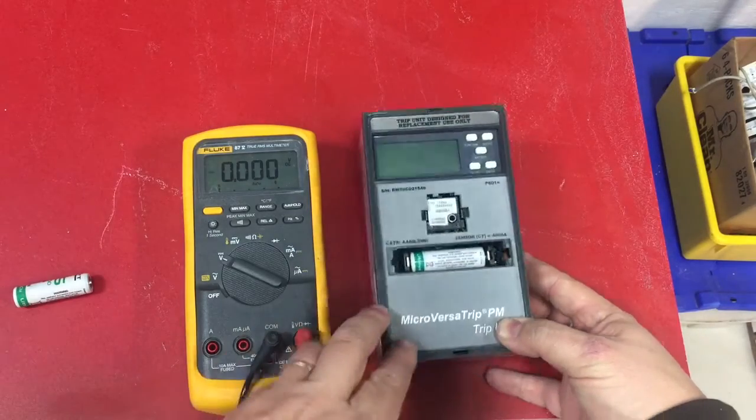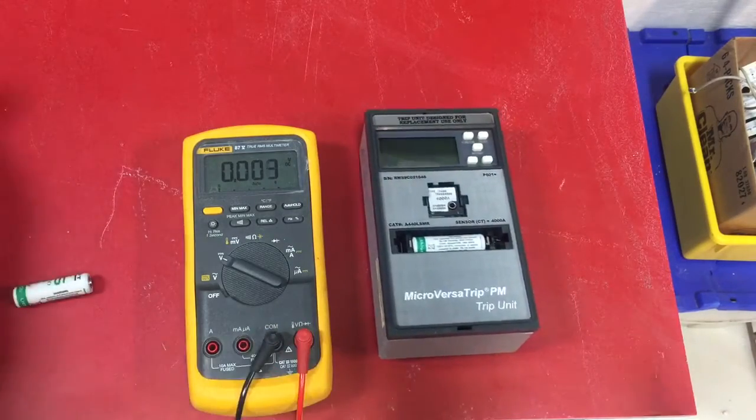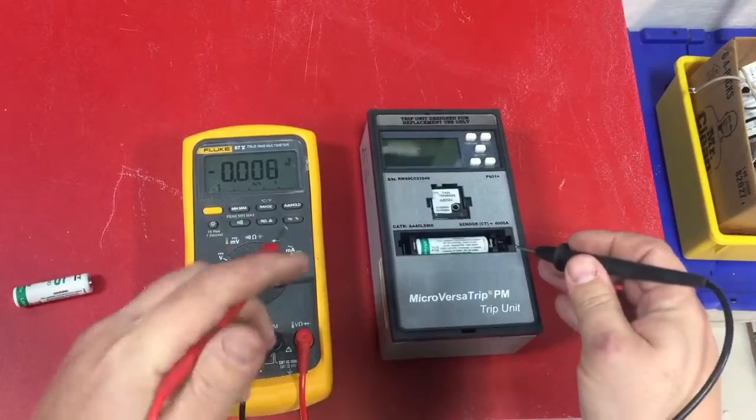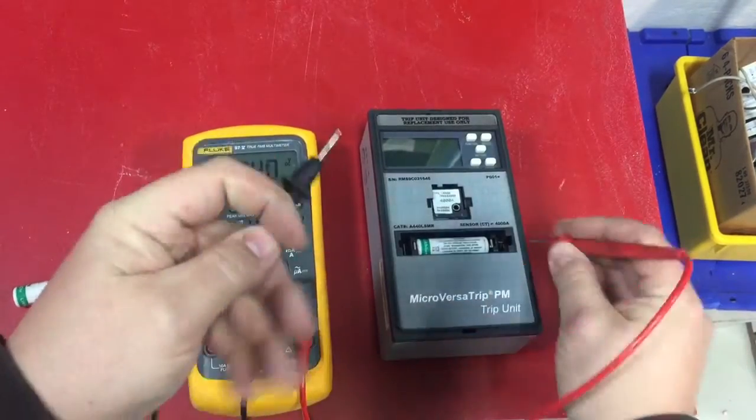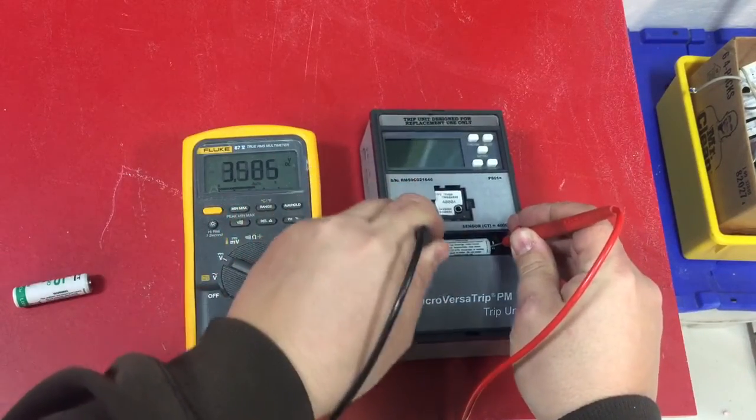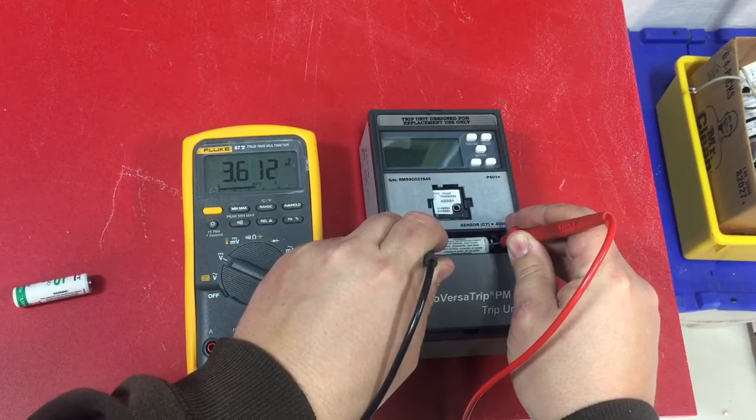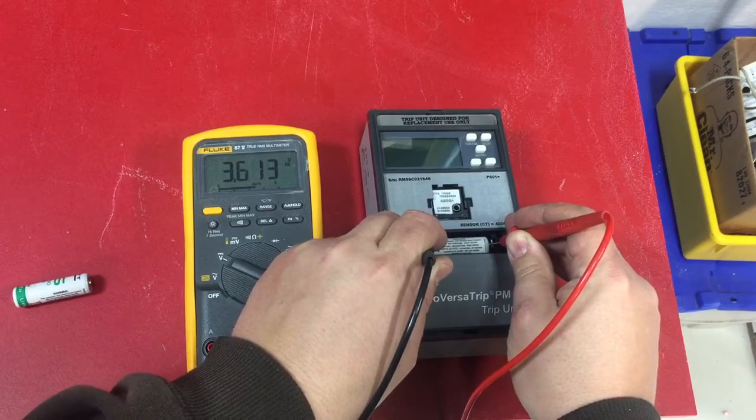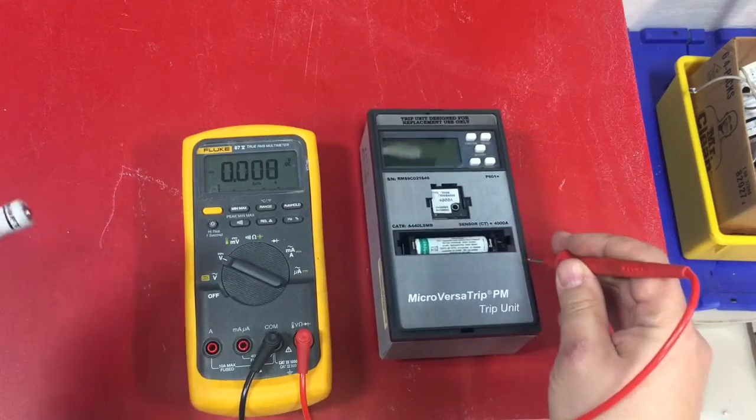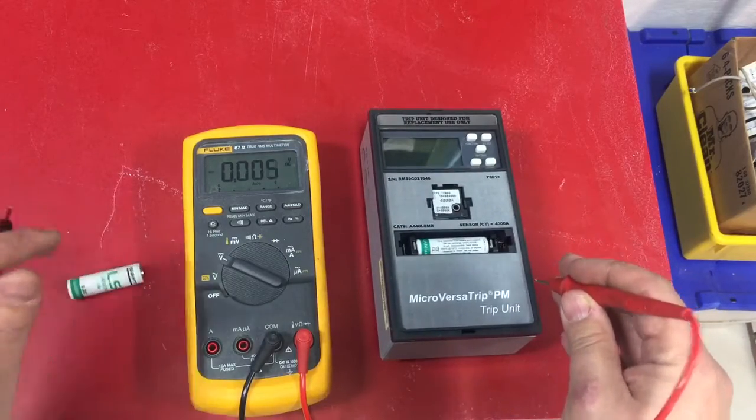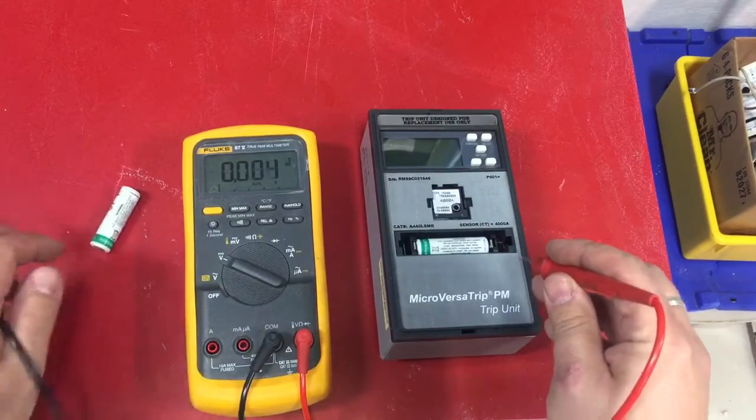So you might think the trip unit's bad, you're not sure. Check the battery. We test the battery like this - that reads 3.61 volts. It's a 3.6 volt lithium-ion battery. Seems like that battery is good, right?